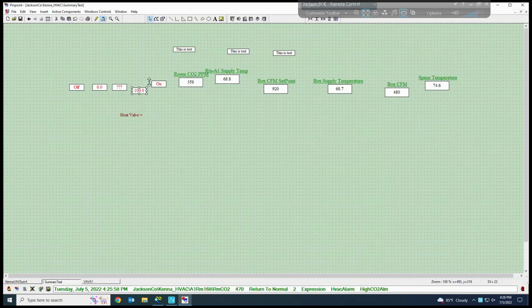Put the airflow set point and the airflow together. Put the things that associate with the other values in an order, left to right, how you would read a book. Here's how: is the fan on? Is it occupied? Is it set? Is the room temperature okay? And all that. That is a better way to do that.